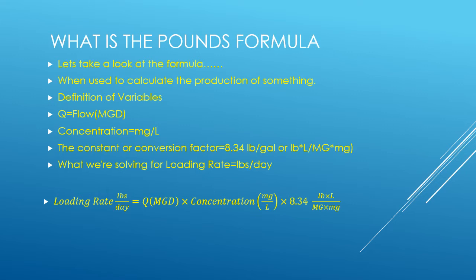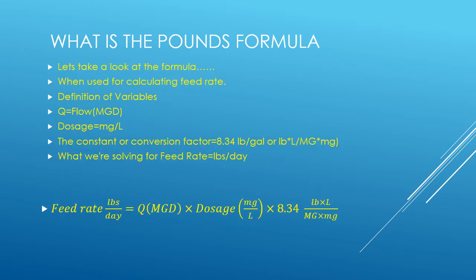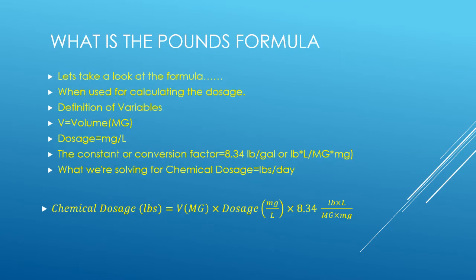Here's another example. We have feed rate, which is also in pounds per day. In this case we have flow, which is still in MGD, and we're using a dosage because oftentimes we use this when we're dosing a flow. And again, the constant, which is always the same at 8.34.